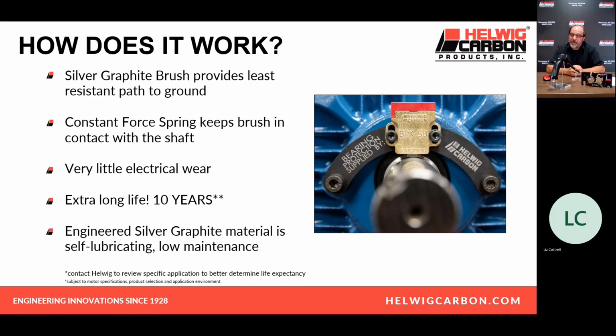This is a set and forget application. Once you put it in, you should not have to do any maintenance to it at all. Never take it off. Never, ever paint colloidal silver on the shaft. Never have to clean the brush path. It maintains its own clean path. It's just what it is.